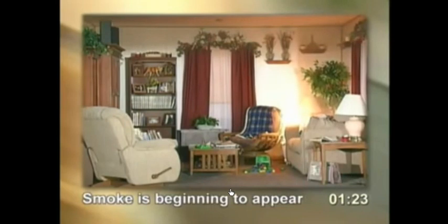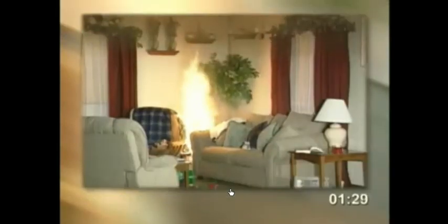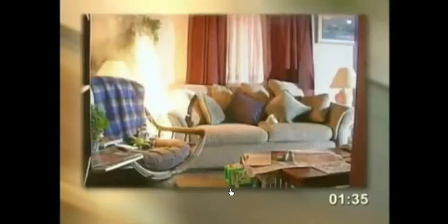So you've got smoke coming in, because the couch is burning and emitting that toxic smoke. As I said before, a very hot smoke, might I add. It's radiating heat back downwards towards the surface of the room, and everything in it is getting preheated by that. So as you're going to see, pretty soon stuff is going to start catching on fire that never made direct contact with the initial flames. And of course, once that happens, it's another heat source and causes the entire room to heat up faster, more smoke to be emitted, and things go in a vicious cycle that ends with everything burning that can burn. That's called flashover.